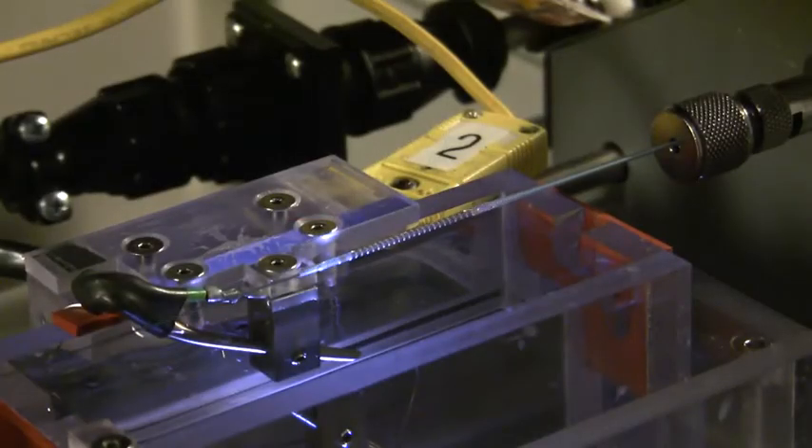To determine foreshortening, the stent is tracked over the guide wire and its length is measured using the high-precision optical measurement system. The stent is then expanded and its length is re-measured. Foreshortening is measured as a difference in length between the unexpanded and expanded stent.